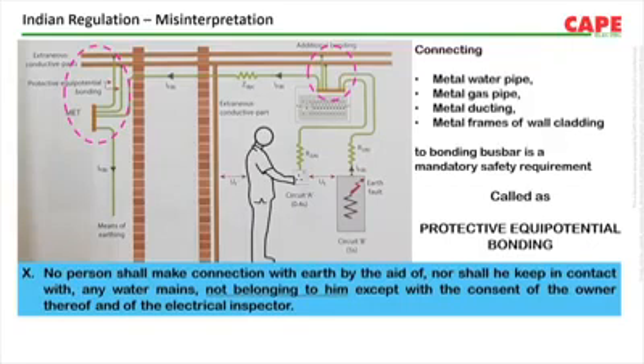The regulation says, no person shall make connection with the earth by the aid of, nor shall he keep in contact with, any water mains not belonging to him except with the consent of the owner thereof and of the electrical inspector. What the regulation says is, if you have a pipe not belonging to you, then you connect it to your earth bus bar with the consent of the owner of that particular pipe. So the regulation is talking about the pipe which is not belonging to you.